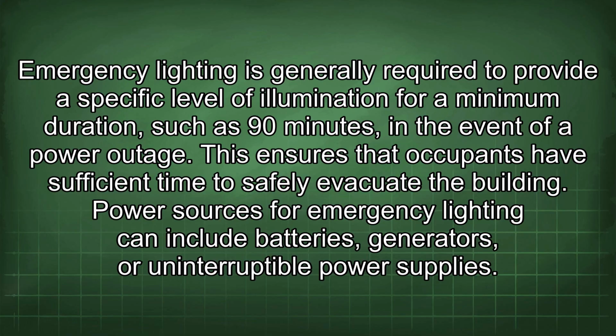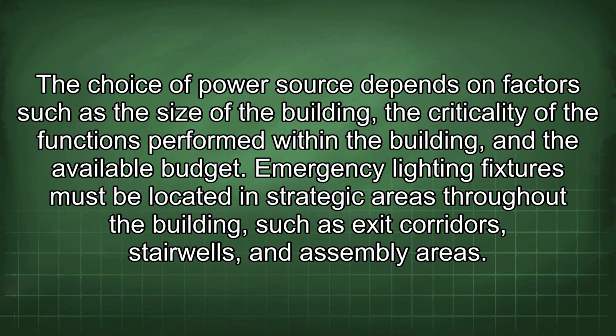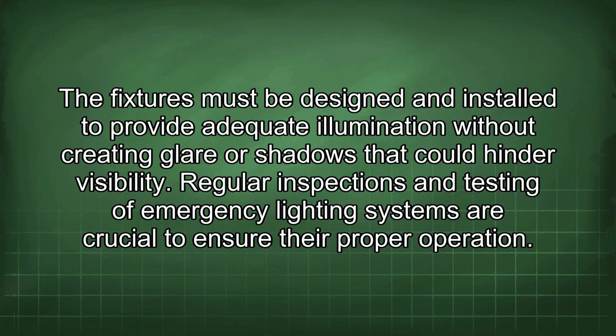Power sources for emergency lighting can include batteries, generators, or uninterruptible power supplies. The choice of power source depends on factors such as the size of the building, the criticality of the functions performed within the building, and the available budget. Emergency lighting fixtures must be located in strategic areas throughout the building, such as exit corridors, stairwells, and assembly areas. The fixtures must be designed and installed to provide adequate illumination without creating glare or shadows that could hinder visibility.